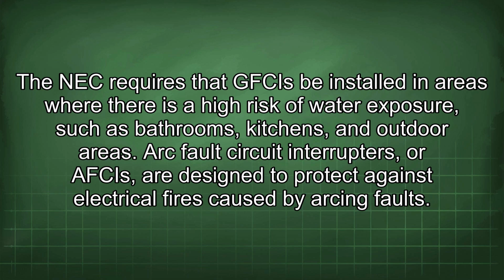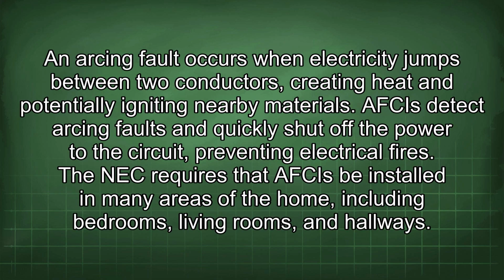Arc fault circuit interrupters, or AFCIs, are designed to protect against electrical fires caused by arcing faults. An arcing fault occurs when electricity jumps between two conductors, creating heat and potentially igniting nearby materials. AFCIs detect arcing faults and quickly shut off the power to the circuit, preventing electrical fires. The NEC requires that AFCIs be installed in many areas of the home, including bedrooms, living rooms, and hallways.